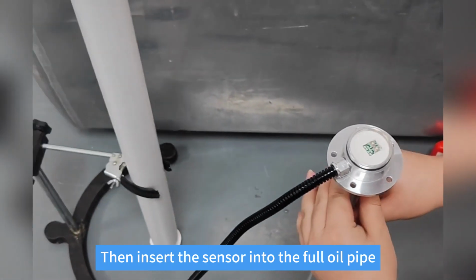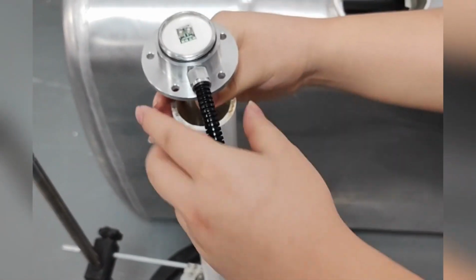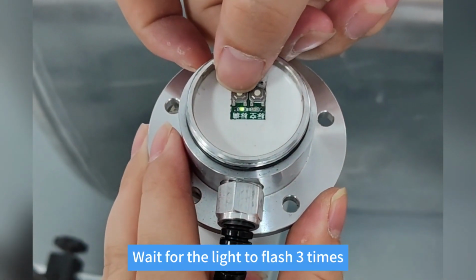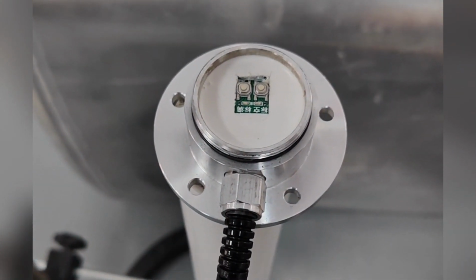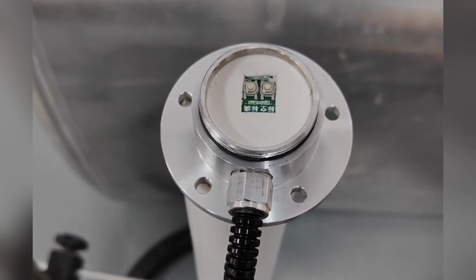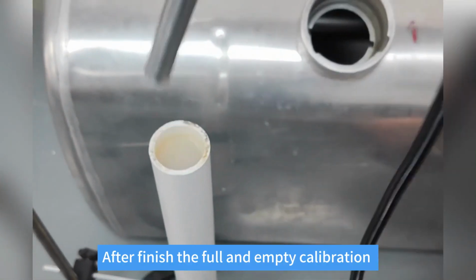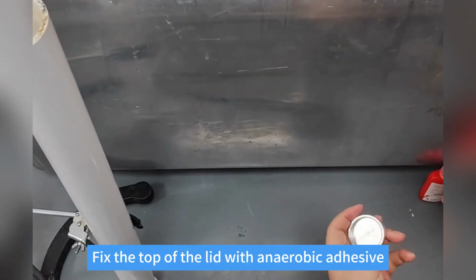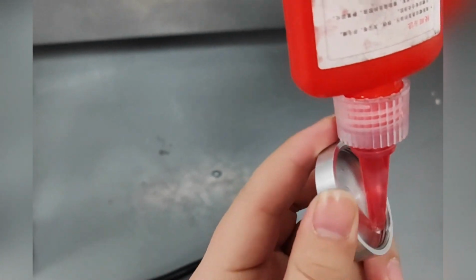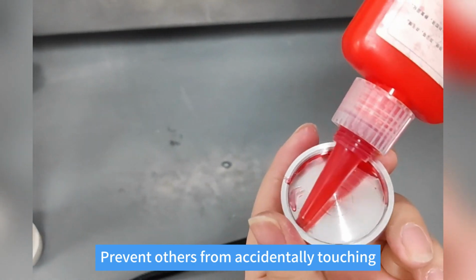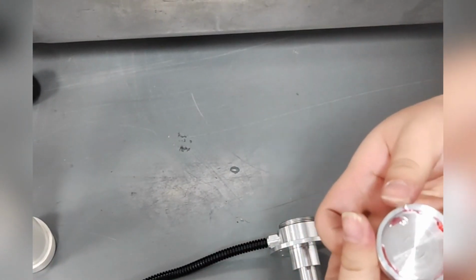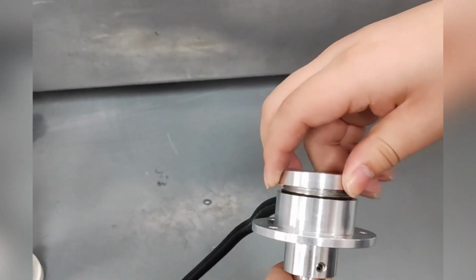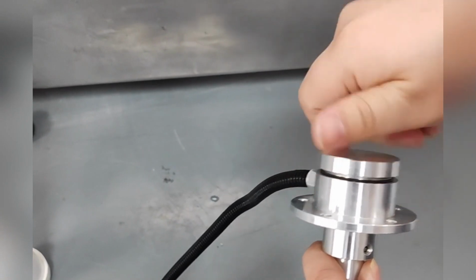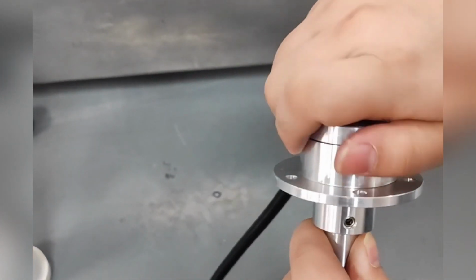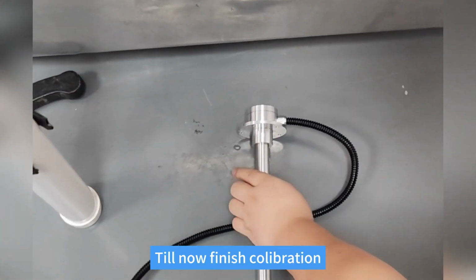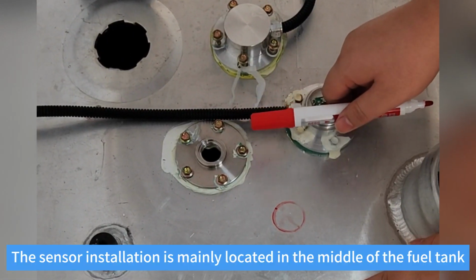Then insert the sensor into the full oil pipe. Press calibrate full button, wait for the light to flash 3 times. Finish the full calibration. After finish the full and empty calibration, fix the top of the lid with anaerobic adhesive. Prevent others from accidentally touching. Till now, finish calibration. The sensor installation is mainly located in the middle of the fuel tank.